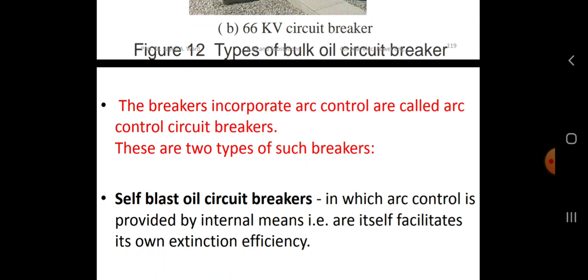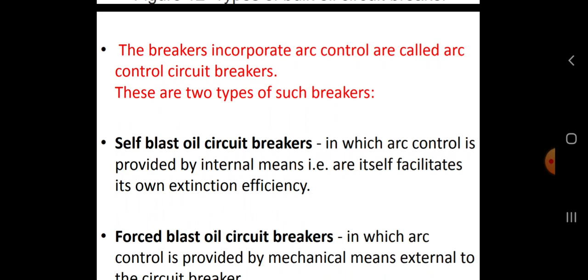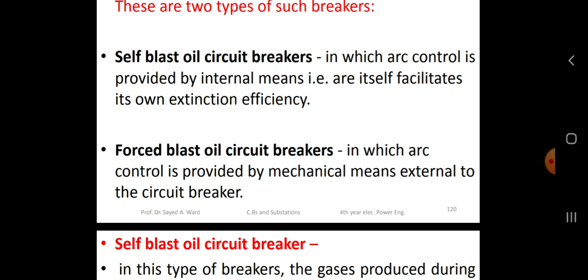The breaker incorporates arc controlled circuit breakers. They are classified into two types. Self blast oil circuit breaker, in which arc control is provided by internal means, or the arc itself facilitates its own extinction. Forced blast oil circuit breaker, in which arc control is provided by mechanical means external to the circuit breaker. Self blast oil circuit breaker.